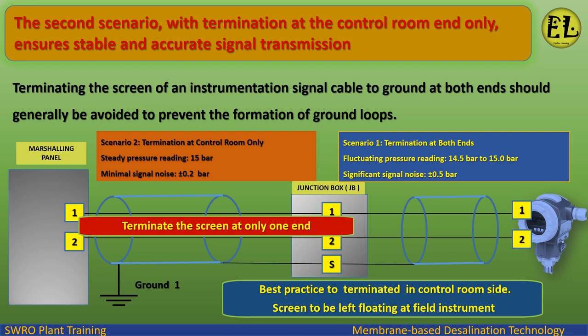Termination at both ends results in a fluctuating pressure reading ranging from 14.5 bar to 15.0 bar, with significant signal noise of plus or minus 0.5 bar.